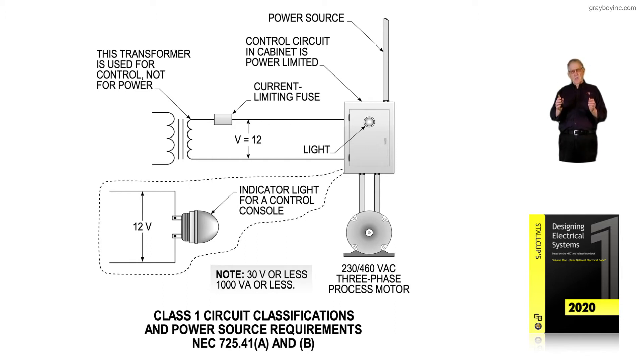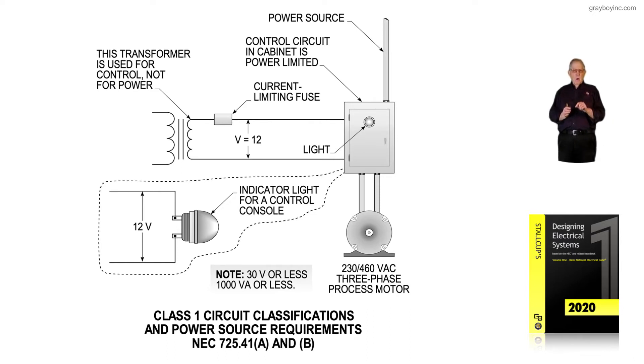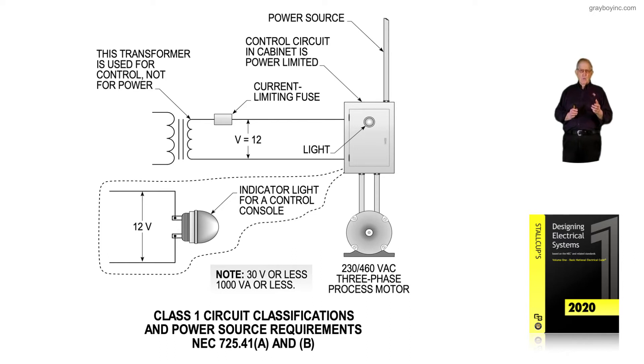We could have a magnetic starter set in accordance with NEC 430.72, and we could have a stop and start button on the cover of your starter, or have remote conductors run out to stop and start stations, pressure switches, or flow switches.